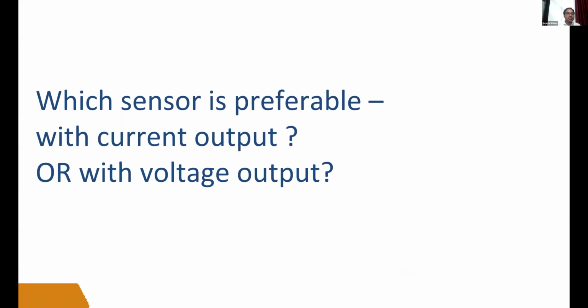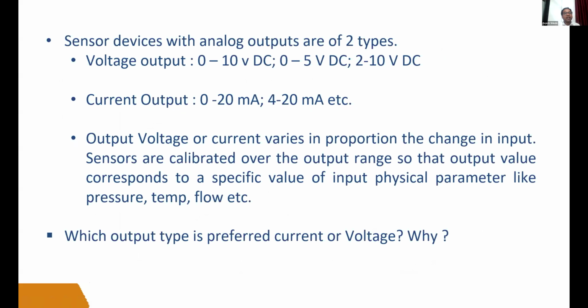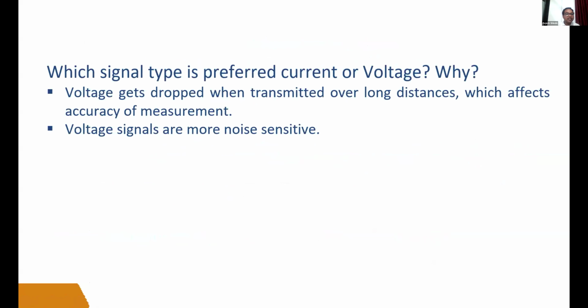Now, if I ask you guys which sensor you will prefer, the voltage sensor or the current sensor? As I already told you, voltage output is given in the form of 0 to 10 volt DC, 0 to 5 volt DC, or 2 to 10 volt DC. And the current output gives 0 to 20 milliamps or 4 to 20 milliamps. Now, if I ask which output type is preferred, current or voltage, your answer would be, guys, the current output sensor you will prefer.